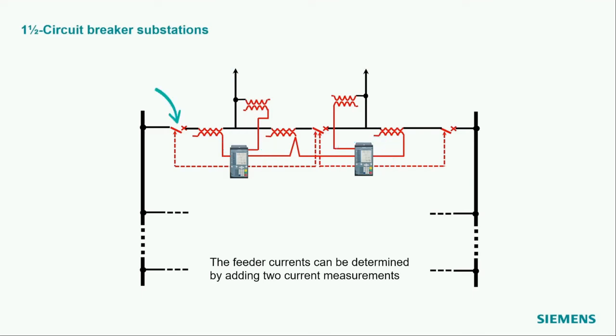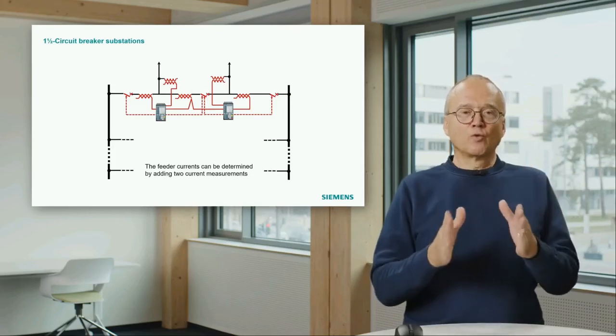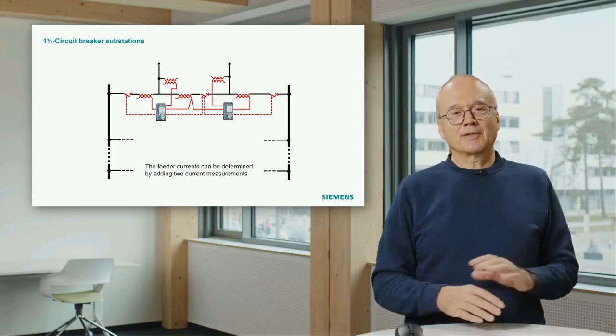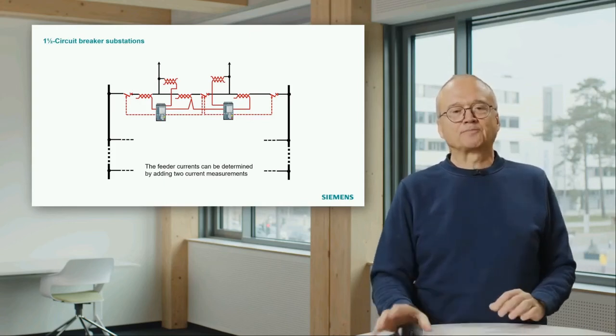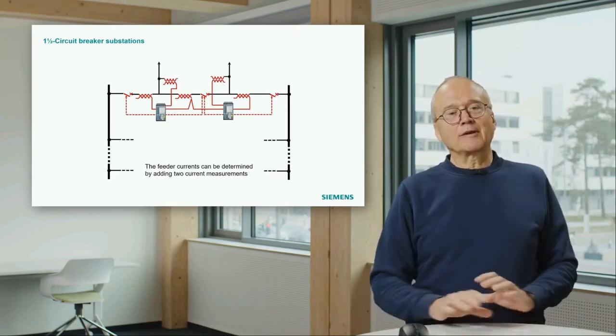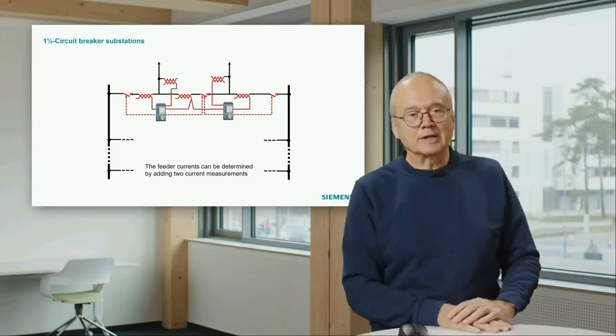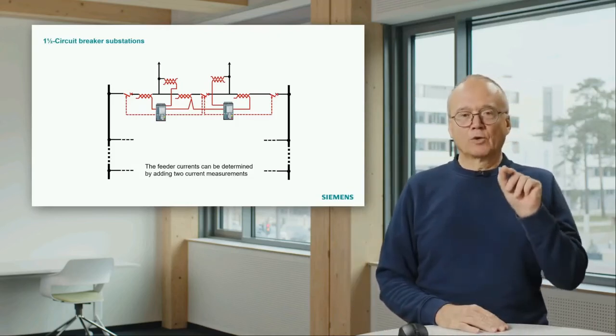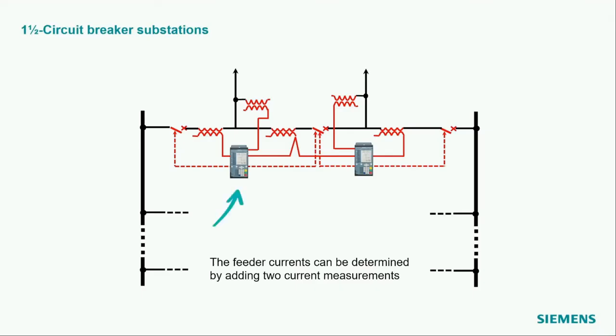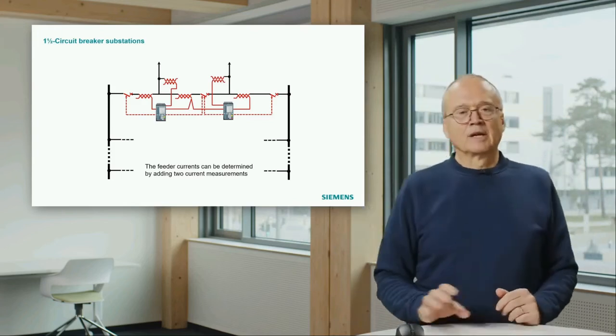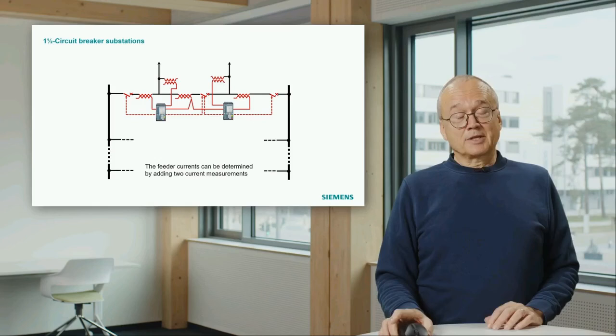But we have in total 1, 2, 3 circuit breakers. That means for 2 feeders we have 3 circuit breakers. That ends up in an average 1.5 circuit breaker per feeder. That means if we look at the left-hand relay, this is responsible for the left-hand feeder. If this relay detects a short circuit on the left feeder, it has to trip 2 circuit breakers, the left-hand circuit breaker and the center circuit breaker. The same applies to the right one. If that detects a short circuit on the right-hand feeder, it has to trip the center circuit breaker and the right circuit breaker. You also see voltage transformers and current transformers here.